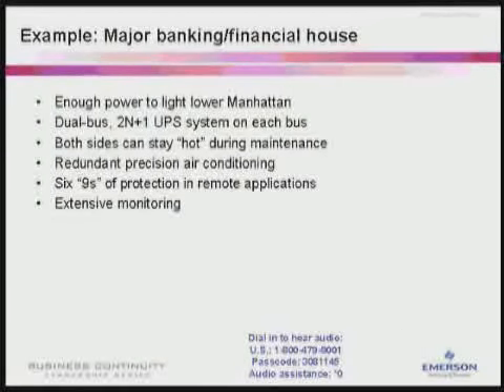Power is monitored from the time it enters the building all the way to the network and computer equipment being powered. Temperature, mechanical issues, humidity, equipment changes, leak detection, and battery life are all monitored. Data is collected and information is used to make preventive repairs and replacements so that failures are avoided.